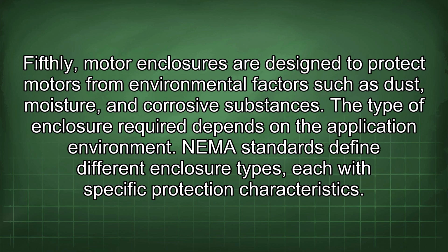Fifthly, motor enclosures are designed to protect motors from environmental factors such as dust, moisture, and corrosive substances. The type of enclosure required depends on the application environment. NEMA standards define different enclosure types, each with specific protection characteristics.